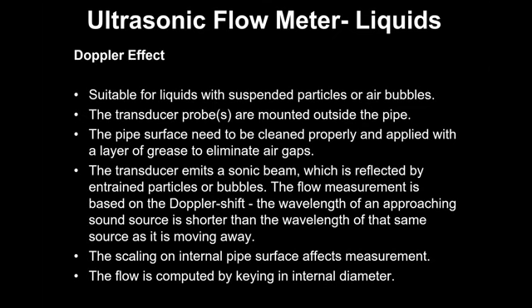Now, the Doppler effect, as I said, is for liquid having suspended particles or bubbles. There can be one transducer or two transducers depending on the instrument. There are instruments available with one transducer, which are slightly cheaper, and these are slightly more expensive. The rest of the things are the same. The functioning is based on the Doppler effect, that is, a shift in the wavelength of sound approaching and leaving the source, and based on that it will do the measurement and tell you the velocity.